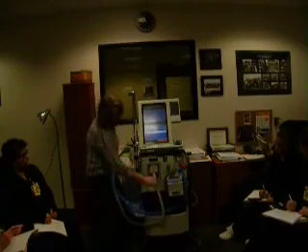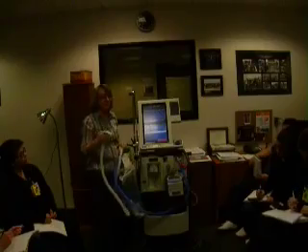So now it says disconnect from patient. From patient means the port coming from the patient, so the exhalation side. So please note my hand is still covering because it hasn't told me to unblock. So you'll disconnect from patient and then hit accept.